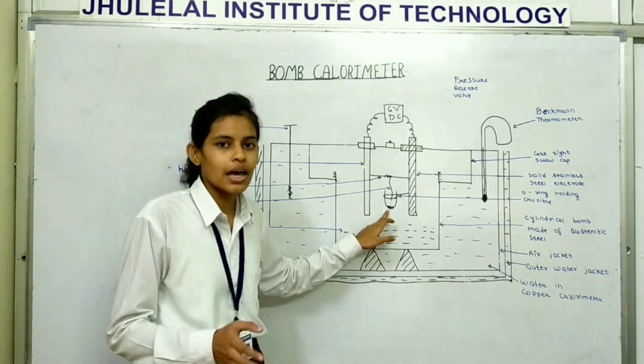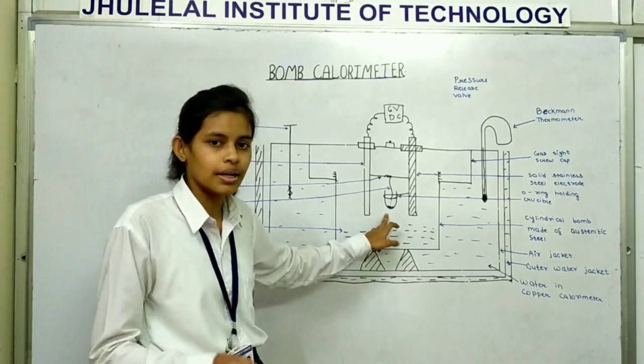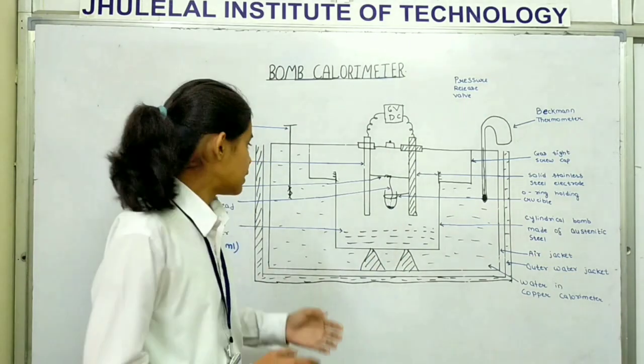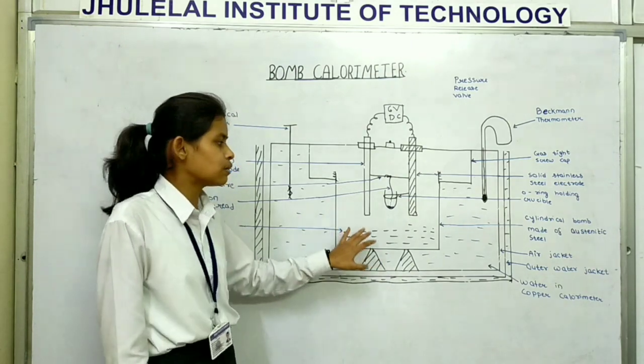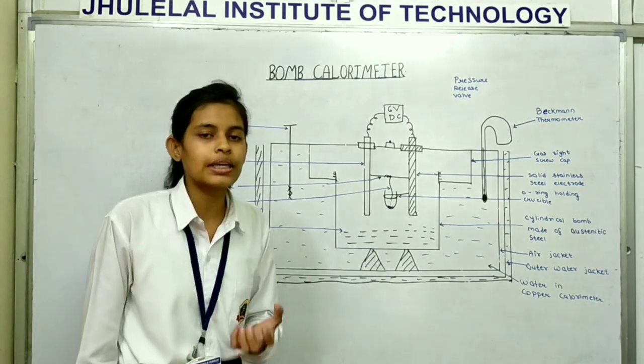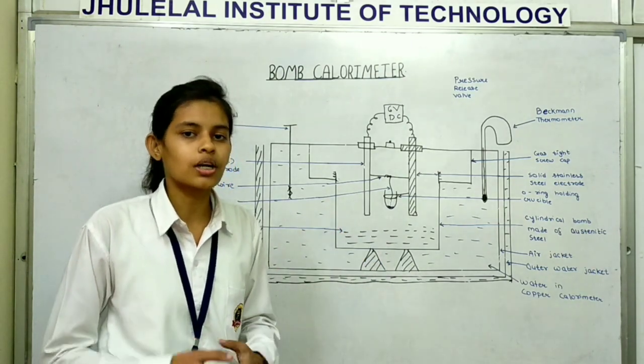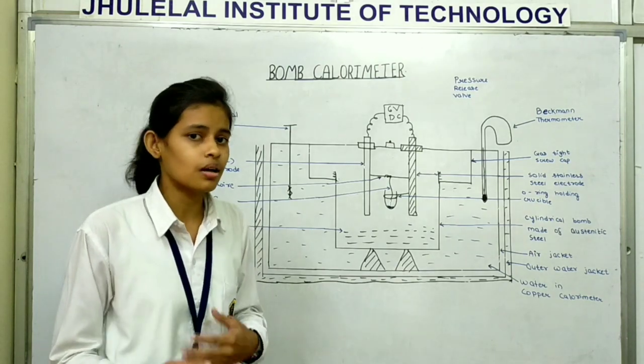One cotton thread is attached to the fuse wire and another is attached to the crucible in contact with the fuel. 10 to 15 ml of distilled water is taken in bomb which absorbs the acid vapor during combustion.